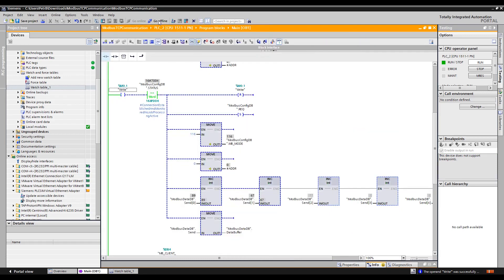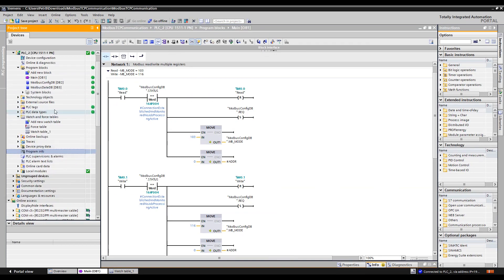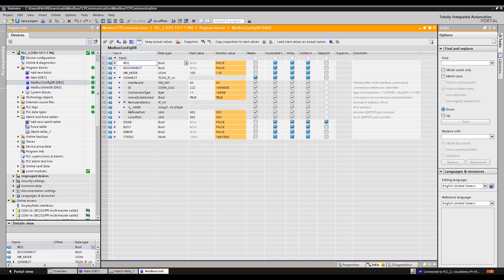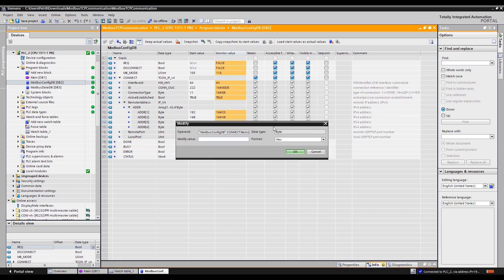This is a working program, but let's simulate some common issues. A frequent mistake is entering the wrong IP address in the connection definition. Open the Config DB, go to Connect, and change the third octet to 1 — making the IP address incorrect.